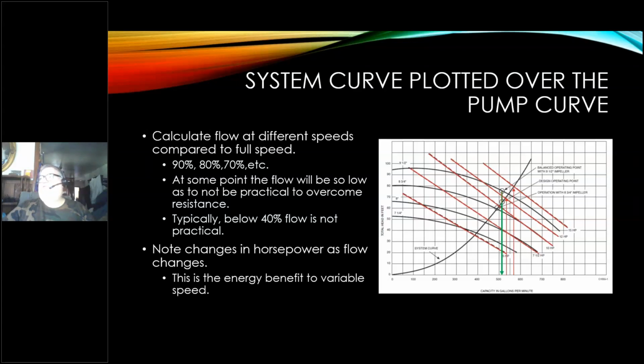Maxed out, though, on that system curve, there are systems where they overspeed the pump above 60 hertz. That's where you have to worry about your horsepower. Did you exceed the horsepower that you have installed when you go above that design point speed to get more water? Or did you reduce the resistance of the system so much that you got above your capacity on your horsepower?